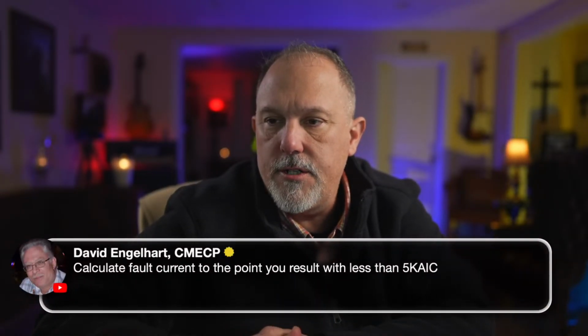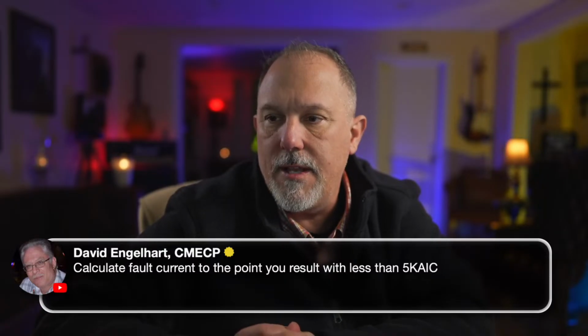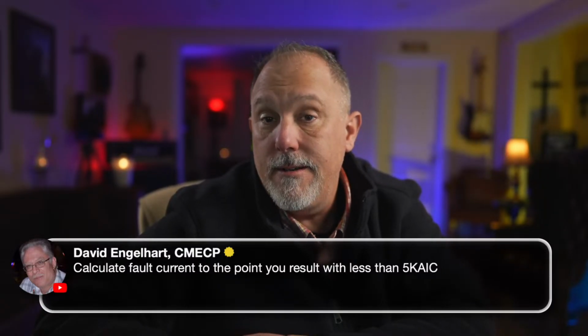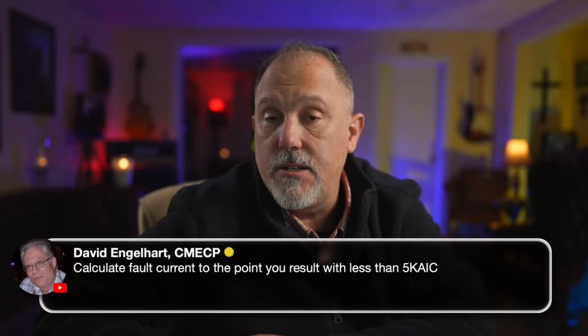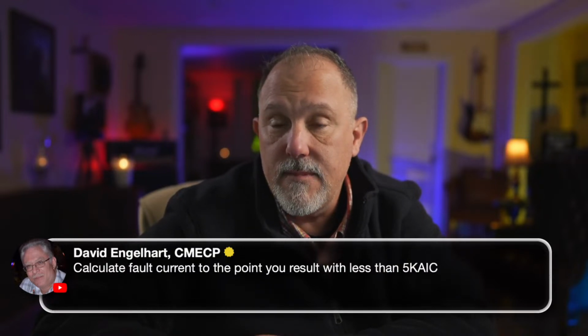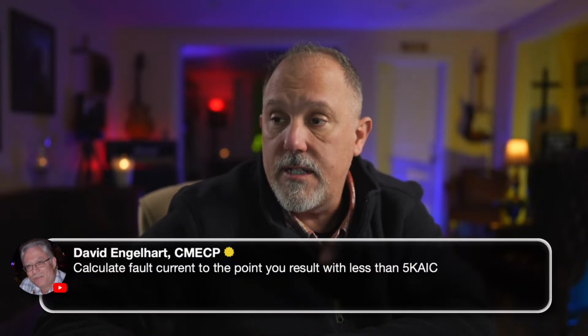Calculate fault current to the point you result with less than 5,000 amps. That's a good philosophy. That's a good philosophy, David. I don't necessarily disagree with you.